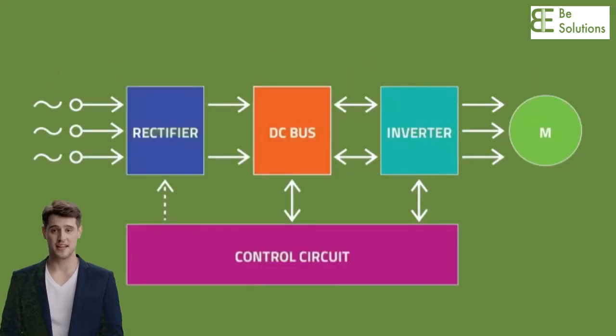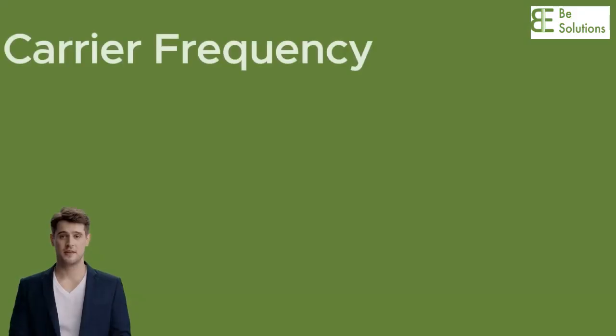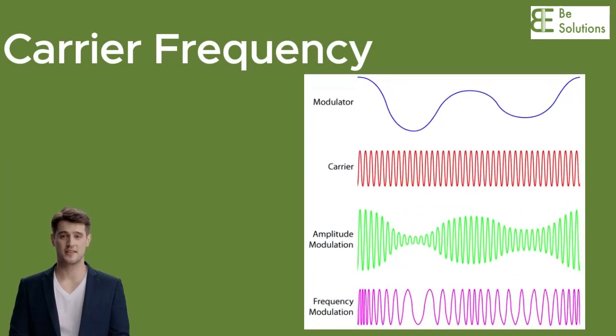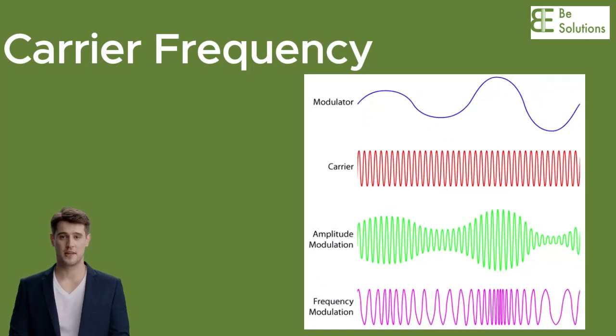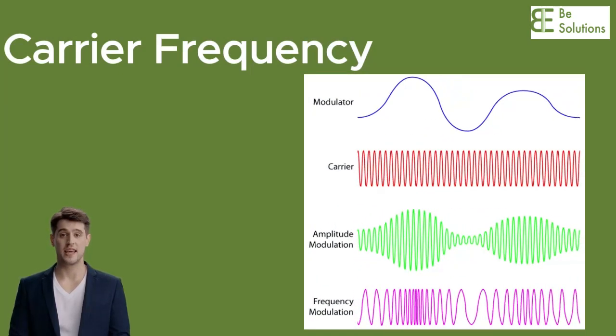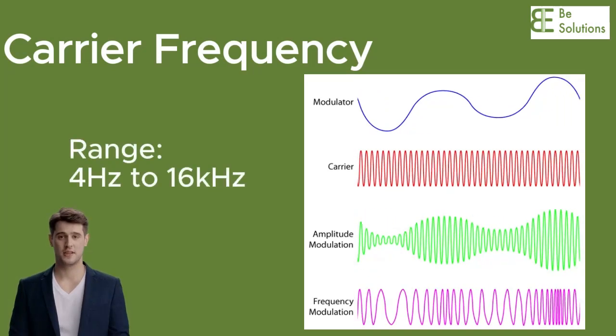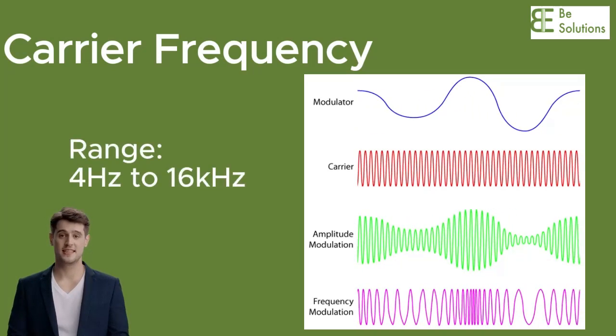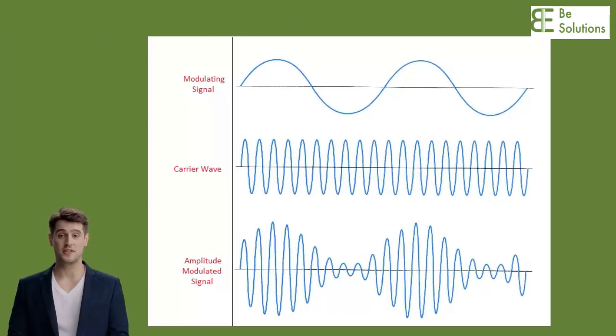A VFD receives power line input at 50 Hz. This is then rectified into direct current. The direct current is further filtered through a combination of an inductor and a capacitor. The frequency at which the voltage pulses are modulated in order to control the speed of the connected motor. The carrier frequency of VFDs typically ranges from 4 kHz to 16 kHz. A higher carrier frequency results in shorter pulse duration, providing more precise control over the output voltage waveform.